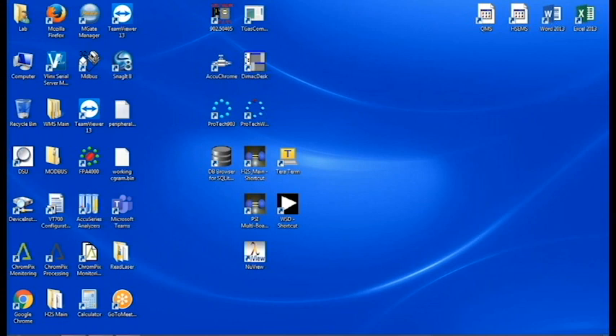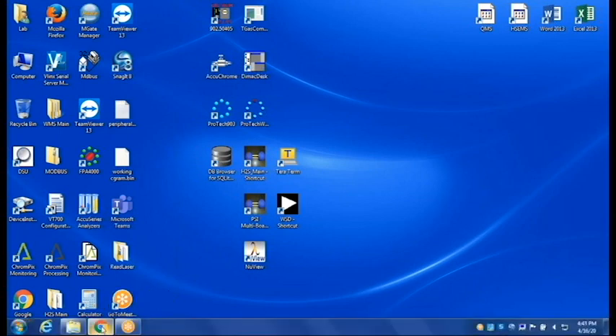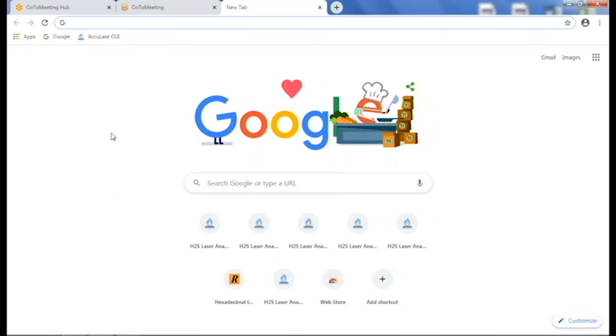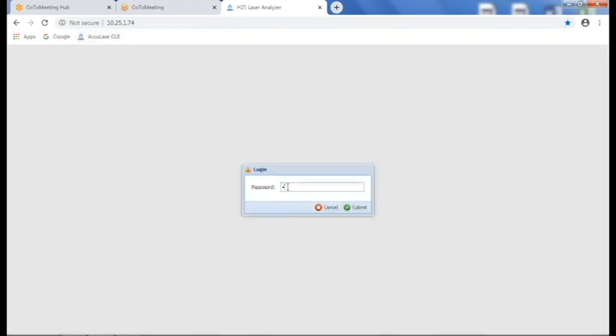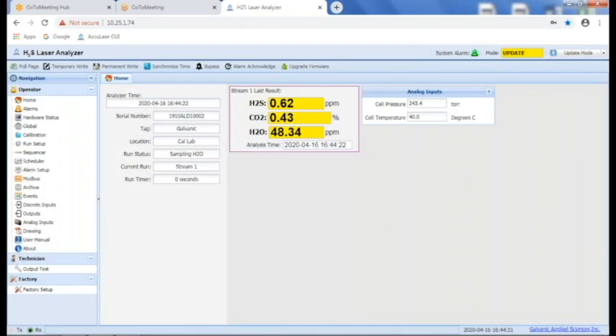So the last thing I wanted to show is a little bit of a demonstration of the actual user interface. This is the remote user interface. So to log in, basically you need a web browser, preferably Google Chrome or Firefox. Internet Explorer, we've found, doesn't work very well, but Google Chrome and Firefox are good options. If you have several units on a network, you can basically tag them on your favorites bar here with their specific IP addresses. I've got mine located here. When you type in the IP address, you get the little splash screen. There's a password. Default password is FACT factory. And you jump in and you can see a bunch of the features of the analyzer.